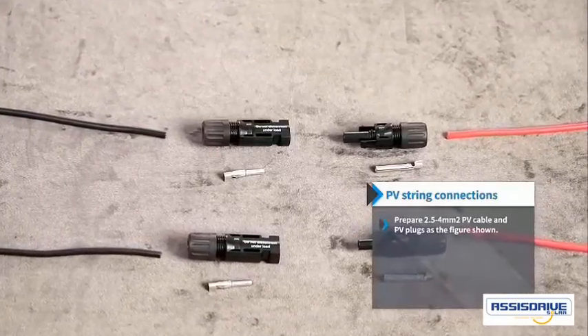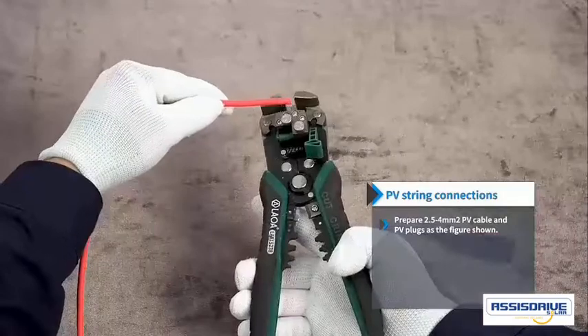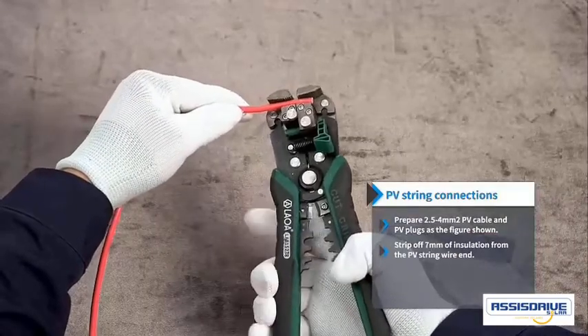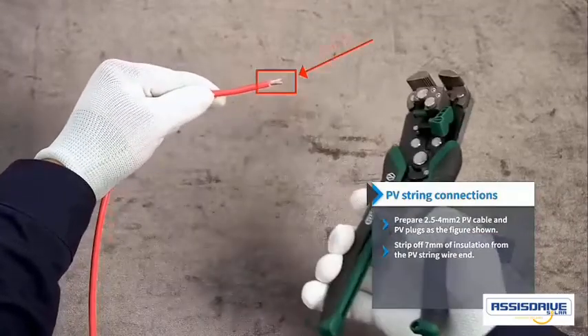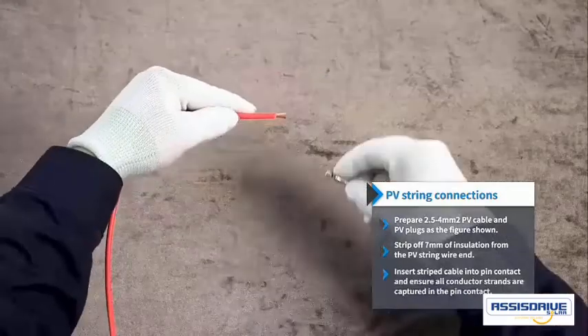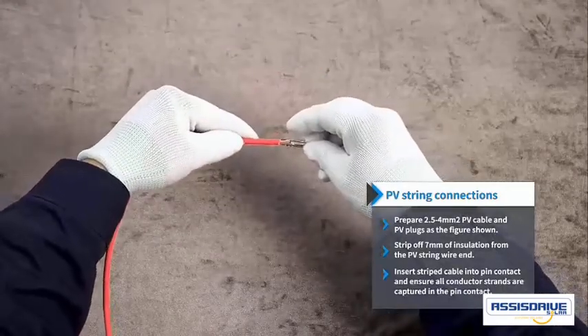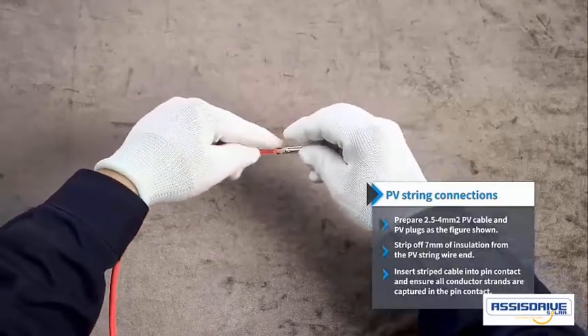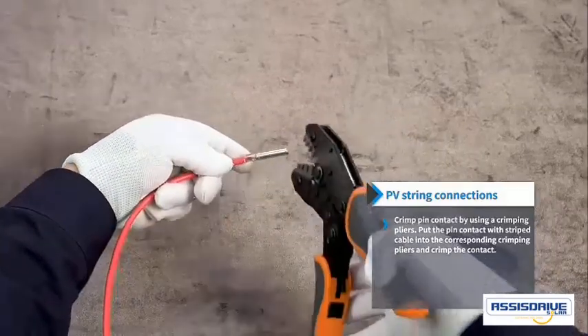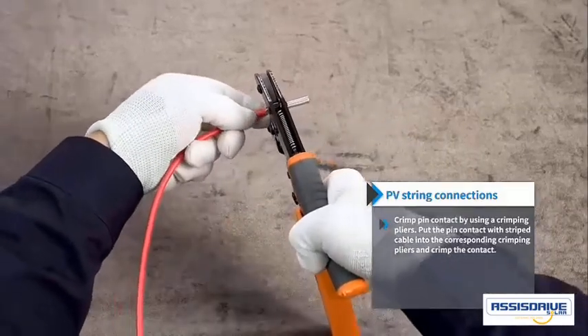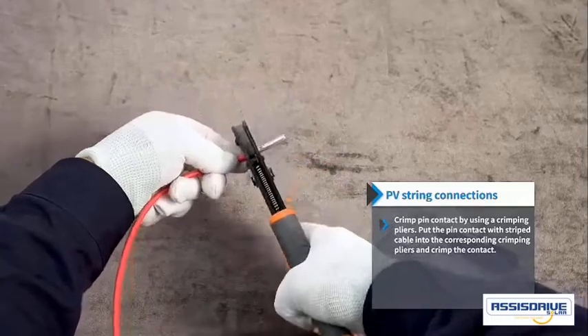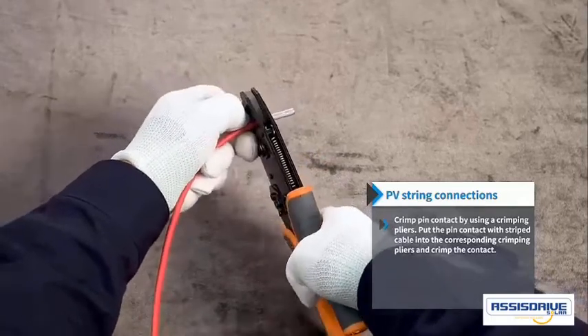Prepare 2.5-4mm2 PV cable and PV plugs as the figure shown. Strip off 7 mm of insulation from the PV string wire end. Insert stripped cable into pin contact, and ensure all conductor strands are captured in the pin contact by using crimping pliers. Put the pin contact with stripped cable into the corresponding crimping pliers and crimp the contact.